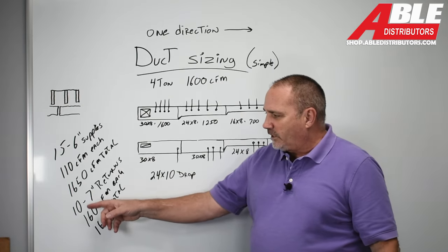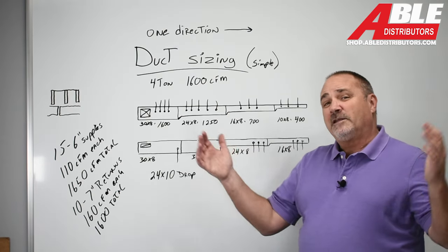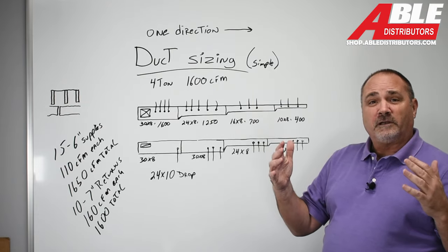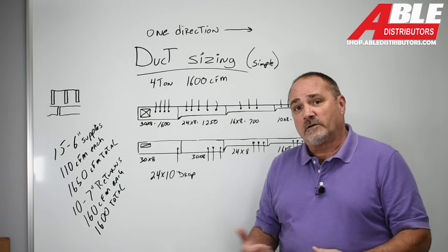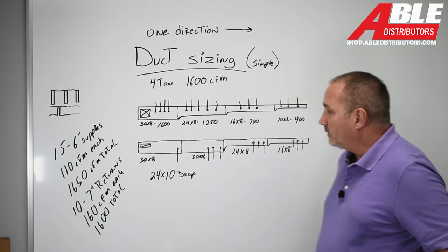And on the return duct, I figured 10 seven inch returns, 160 CFM a piece. Again, typically those runs are shorter because they're on inside walls. So you can actually get closer to 160 CFM out of each one for a total of 1,600. So let's get started.